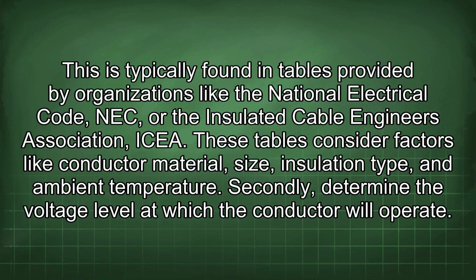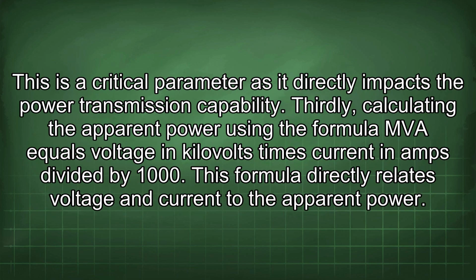Secondly, determine the voltage level at which the conductor will operate. This is a critical parameter as it directly impacts the power transmission capability. Thirdly, calculating the apparent power using the formula MVA equals voltage in kilovolts times current in amps divided by 1000. This formula directly relates voltage and current to the apparent power.